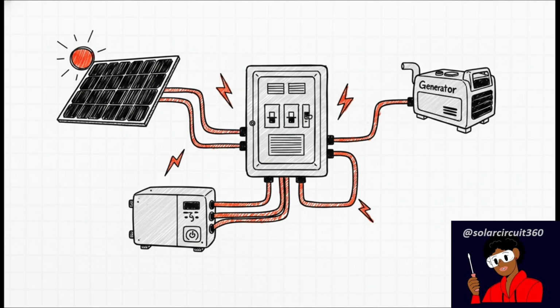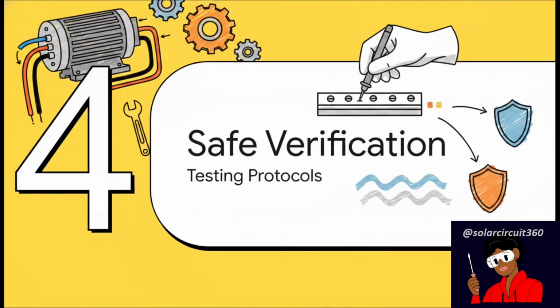Or during backup power integration, the phase sequence coming off a standby generator might not match the utility supply. Actually, it could be as simple as incorrect phase connections during a brand new solar install, or just conductors getting accidentally crossed in an electrical panel during some routine maintenance work. Because the source of our power is constantly evolving in today's microgrids, the risk of a phase rotation mismatch is honestly higher than ever. Let's get into Section 4, Safe Verification and Testing.